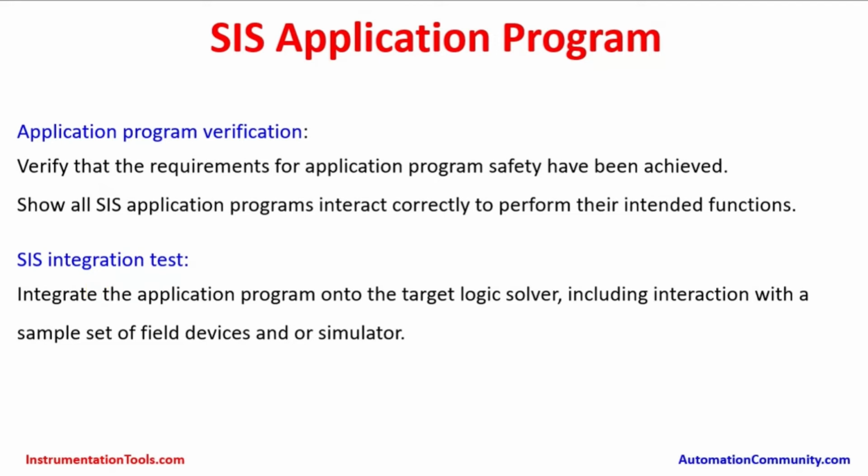Integrate the application program onto the target logic solver, including interaction with a sample set of field devices and/or the simulator. This is like uploading the program to the respective processor and then verifying the healthiness of those processors by giving a simulation in the field for the input, selecting the right valve to operate and reviewing the output. This is one of the requirements to do an integration test when all the sensors, SIS logic solvers and final elements are placed in line.